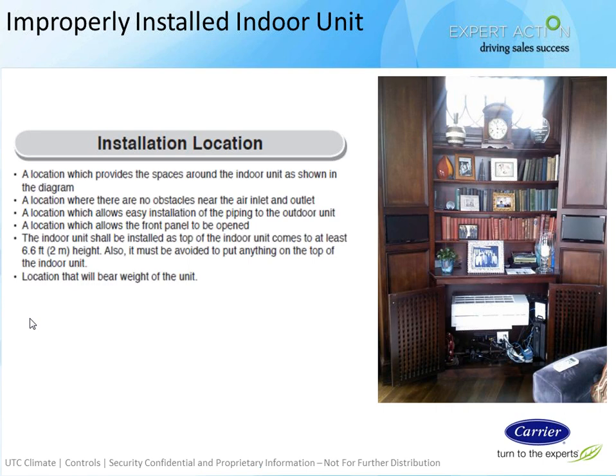Again, another real job where the contractor or the owner decided to put it in there. It was a problem job that had to be fixed. It voided the warranty. Again, just read the instructions. These things are pretty easy to install, but you do have to sometimes say no to the customer. So, a location where there's no obstacles near the air inlet or outlet, and where you have easy access for service. And they're called high walls because they must be mounted relatively high up on the wall, at least 5 to 6 feet off the floor.